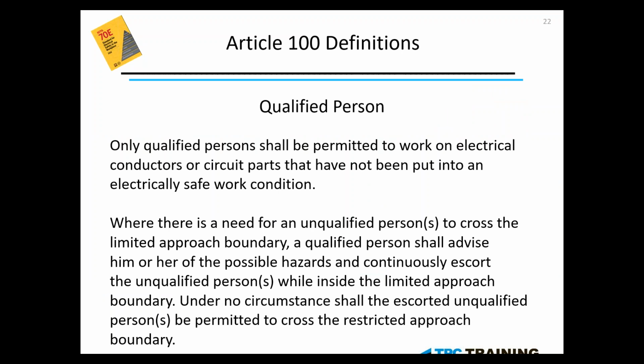Again, the definition of qualified person pops up. Only qualified persons shall be permitted to work on electrical conductors that have not been put into a safe working condition. Towards the bottom of that, I wanted to bring this slide up to point out that under no circumstances shall the escorted unqualified person be permitted to cross the restricted approach boundary. So there is one exception that applies to the qualified person or an unqualified person crossing into these boundaries. They may do so while under the direct supervision of a qualified person for training purposes, but under no circumstance will they ever cross the restricted approach boundary.